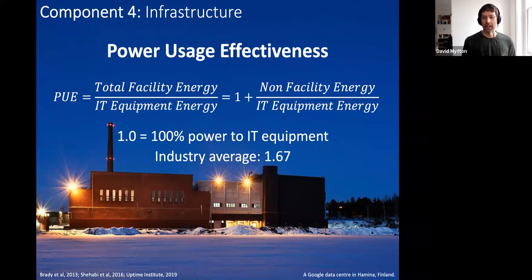Larger data centers tend to have lower PUE ratios, which usually means they're more efficient. However, using PUE alone has been criticized because it can be lower when IT load increases. So it's a useful metric for understanding efficiency improvements within a data center, and is often used to compare between data centers, although it wasn't designed for that, but it doesn't necessarily indicate efficiency by itself.